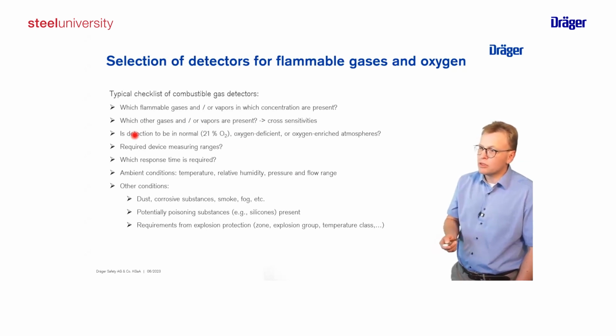We need to know what kind of flammable gases or vapors are present and in which concentration, because this defines which technologies you can use. Are there other gases or vapors present, because you have cross sensitivities, or maybe you need to select a different calibration? We always need oxygen in a sufficient amount, and not an oxygen-enriched atmosphere, because this leads to other effects. What is the measuring range? That means what concentration the device should indicate.